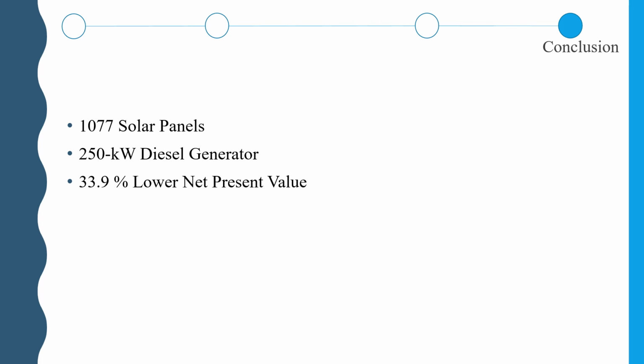Based on the Homer Pro software results, the most reliable and economical design of the hybrid system which would provide the required electrical power for the load of the community of Grey River would be the combination of solar energy and diesel energy. The results of Homer Pro software show that the average daily load of 1632 kilowatt hours would require a total of 1077 solar panels, which would provide a maximum of 381 kilowatts, while a 250 kilowatt diesel generator would supply the rest of the load. The hybrid system net present value was 33.9% lower while the levelized cost per kilowatt hour was 34% lower when compared to the diesel-only system.